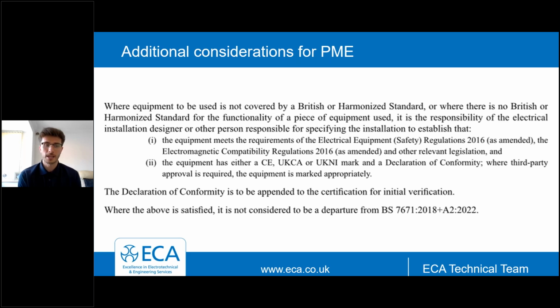So it's important when you're selecting this equipment, you're obtaining the information from the manufacturer and handing it over as part of the handover process with your initial verification documentation. Additionally, what we've also found is sometimes that designers and installers are assuming that this open-PEN device is fitted within the EV charging equipment, and they're not carrying out their due diligence and not carrying out the checks and confirming with the manufacturer that that protection is provided.